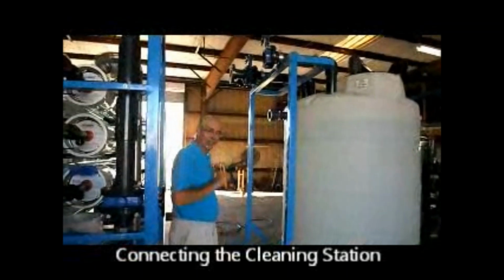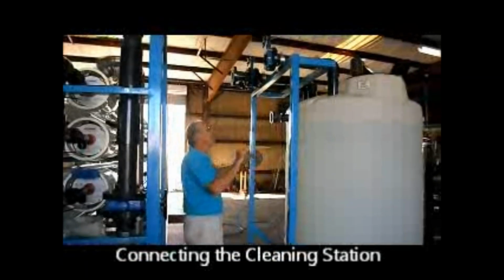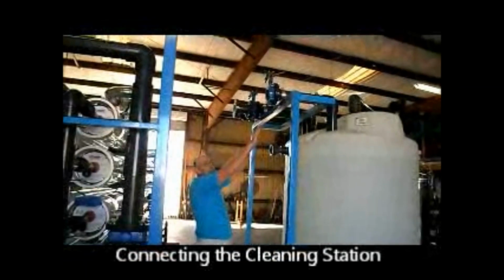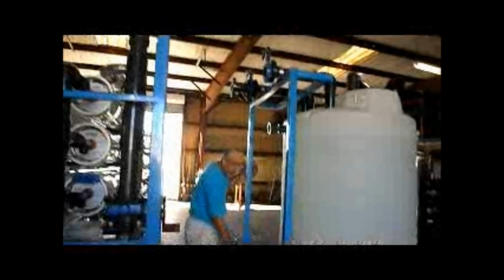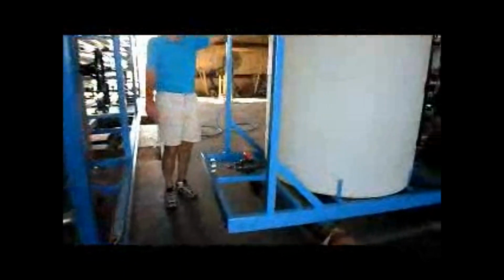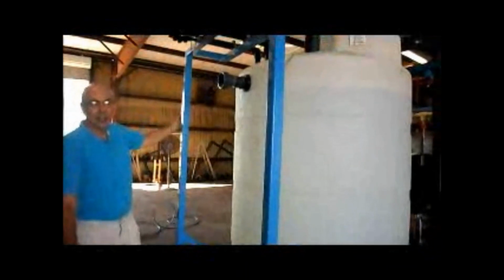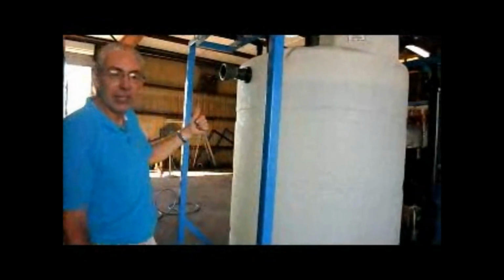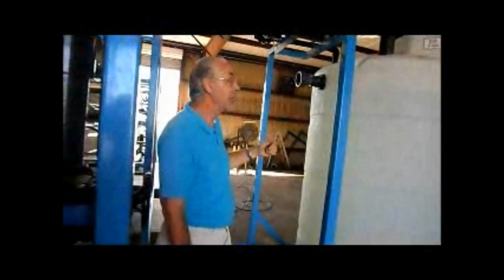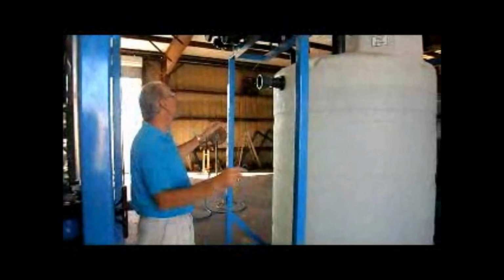5 connections for the cleaning system. 3 primary ones on this side, and the drain. And over on this side of the machine is the outlet from the cleaning station to the RO or EDI skid. Let me explain these 3.